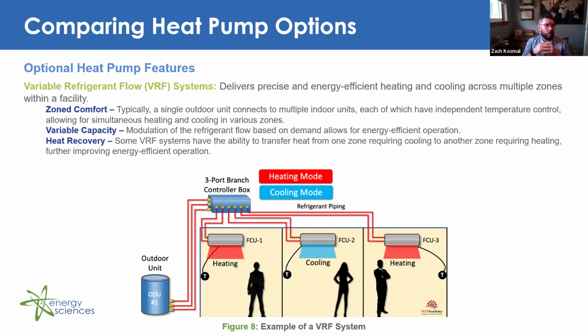And that just allows for a more energy efficient operation. And lastly, you can also have heat recovery, where some VRF systems have the ability to transfer heat from one zone requiring cooling to another zone requiring heating. This also furthers your energy efficiency. And you can see in figure 8, that is one example where you can see that center FCU, it's in cooling mode, and the other two surrounding it are in heating mode. So you can kind of share that heat transfer between different zones for a more efficient operation.